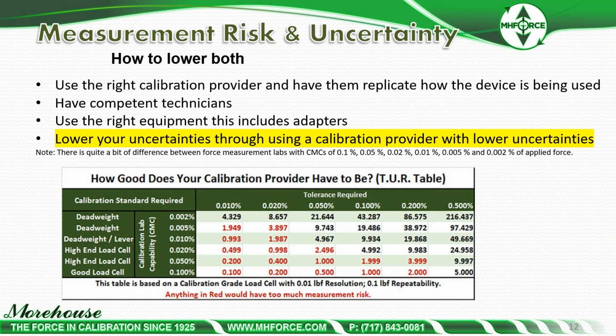So it really shows that if you want a tighter tolerance, a tolerance of better than 0.02%, you really need to use dead weights. Even if you want a tolerance of better than 0.05, you almost in all cases need to use dead weights.